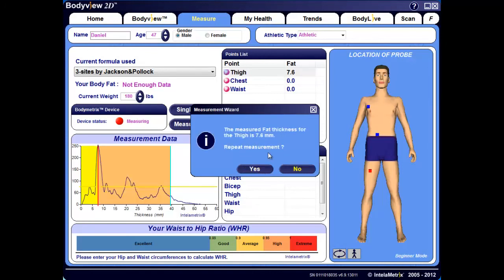When the two measurements are completed, the software gives you the option to repeat the measurement or not. It's always a good idea to examine your measurement data graph to ensure that the software has chosen the correct ultrasound peak. In this case, we can look at the graph and that first strongest peak lines up very nicely with the red vertical line, which is an indication of a good, accurate measurement. So in this case, it's not necessary to repeat the measurement — we'll go ahead and select No.